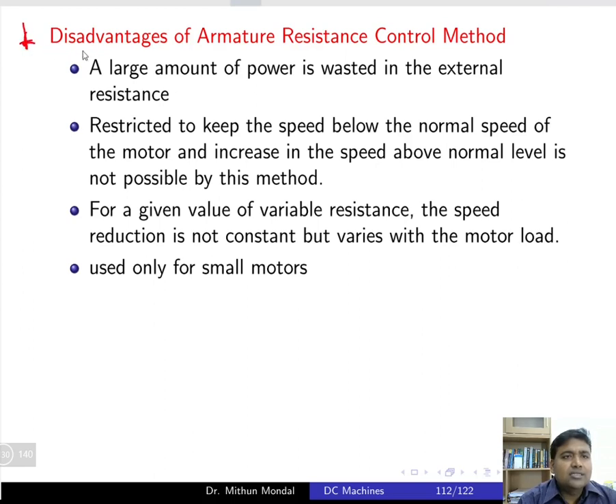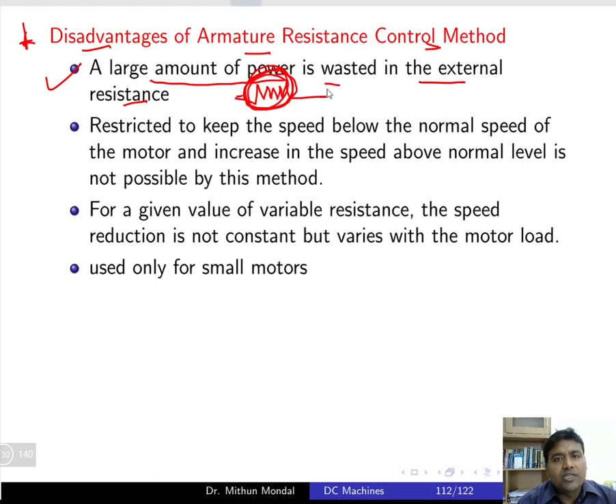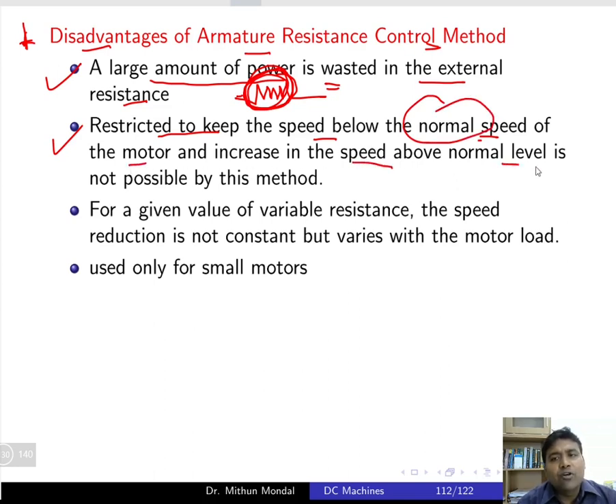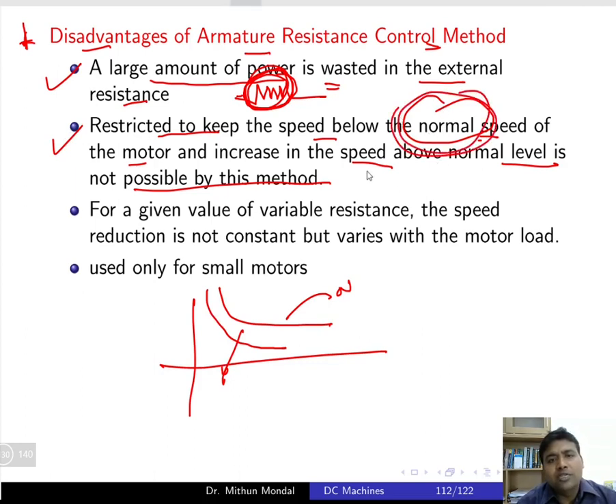There are certain disadvantages of the armature resistance control method. First, a large amount of power is wasted in the external resistance — there is heavy power loss in the rheostat. Second, this method is restricted to keeping the speed below the normal speed. The characteristic always falls below the normal operating point, so increasing speed above normal level is not possible with this method.